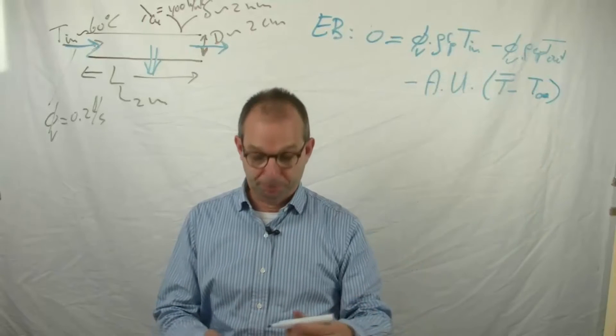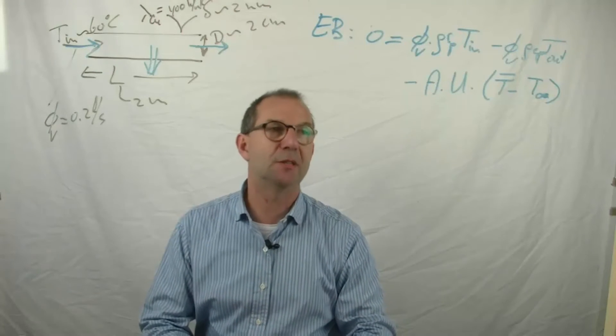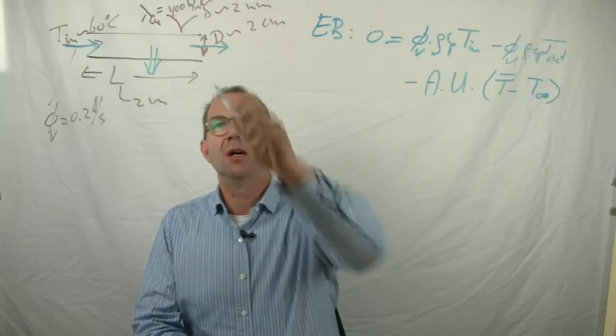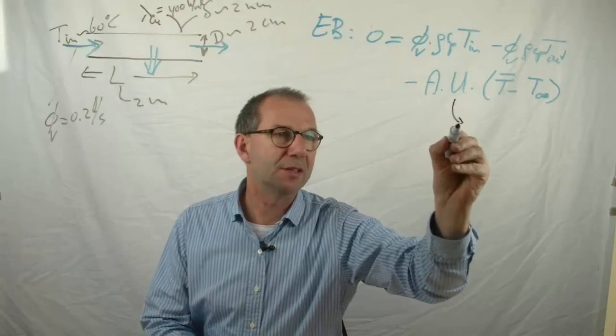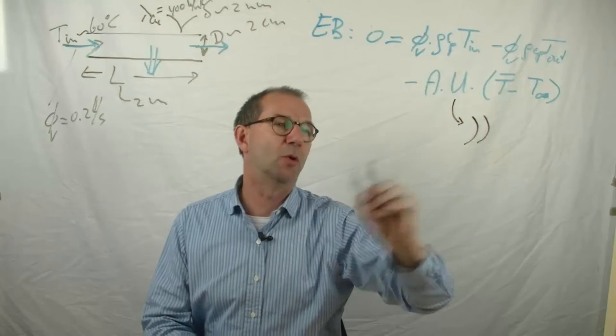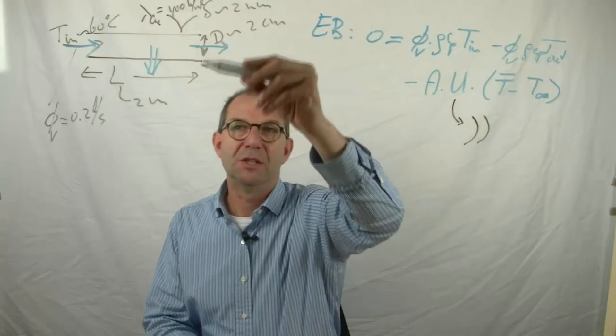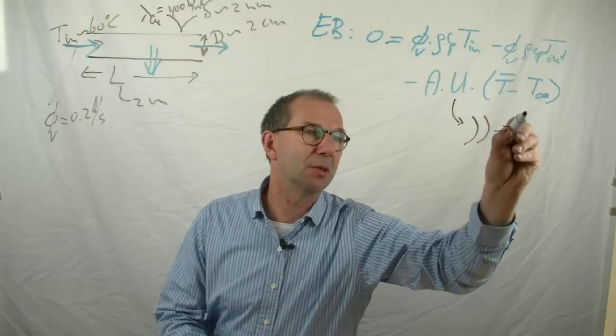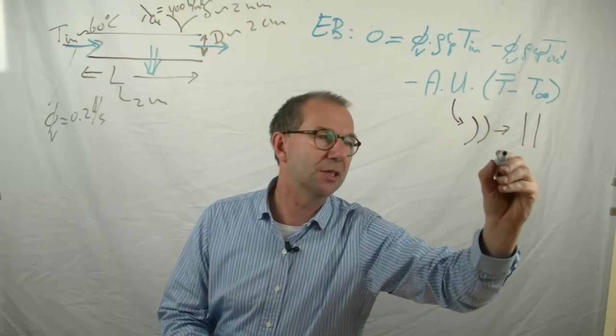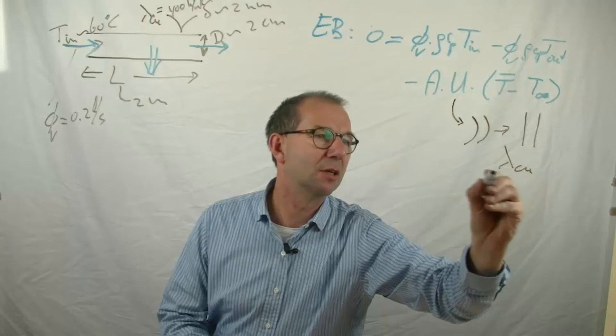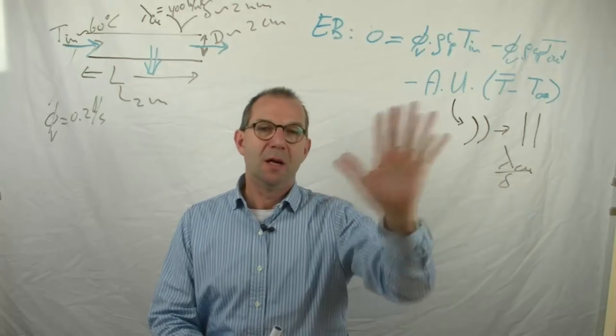This is still generic. Now I'm going to assume first that there is no external heat resistance — all heat resistance comes from the copper — that's the worst case. This is a curved wall, heat is going through it, but the wall is relatively thin compared to the diameter of the tube. So for a first estimate I can treat this as a thin flat plate. Thus U is estimated as lambda of copper divided by the thickness delta, the thickness of the wall.